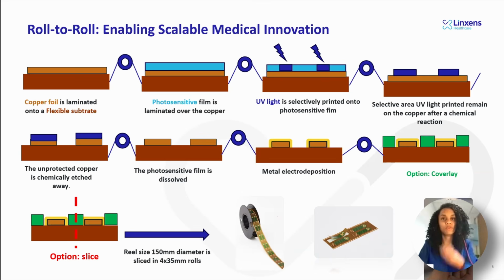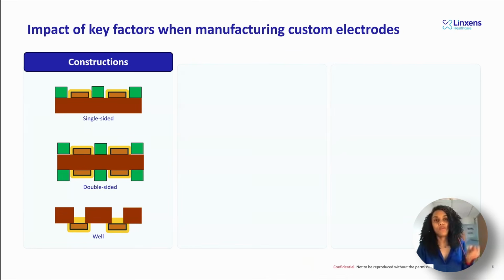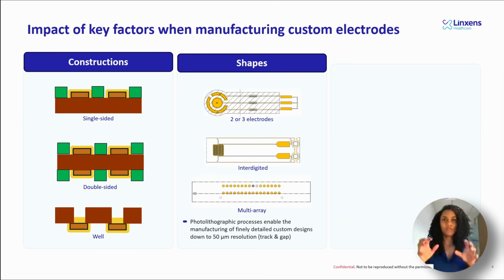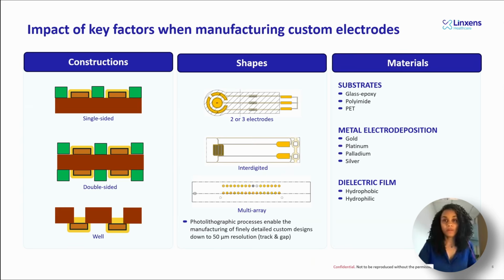So this is the roll-to-roll manufacturing process that we apply, that we use for the electrode manufacturing by strip. So with this system, we can obtain different constructions. So we can have a single side, double side, well system. So it will depend on the demand from our customer. We also have, thanks to the photolithographic system and the etching of the copper, the ability to obtain different shapes. And we have a limitation on the design. We can go down to 50 micrometer in resolution. And we work with different materials. So in function of your need, in function of your specification, we can use different materials. The only constraint is the fact that we need to have a flexible substrate. So we are not working on rigid substrate.